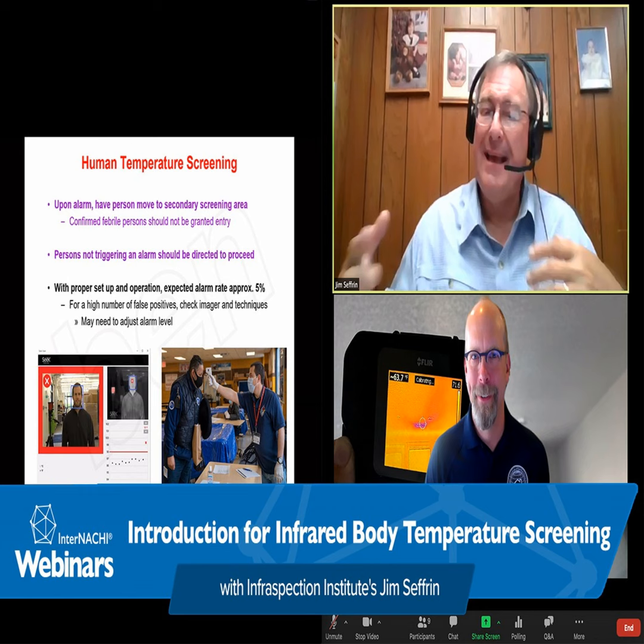If you have a cooled system, chances are it's going to be far more expensive, oftentimes exceeding several tens of thousands of dollars for those instruments. But either one, no matter what you have, is acceptable. At present, uncooled systems constitute nearly 100% of portable imagers available commercially. You also need to select a thermal imager with sufficient image quality and measurement accuracy. This is determined by the detector inside the instrument and the optics attached, and also proper imager use.